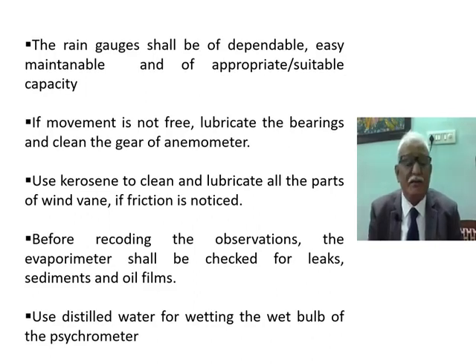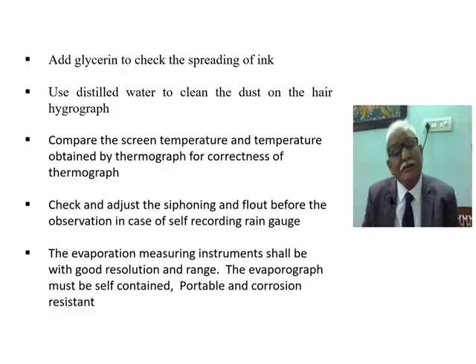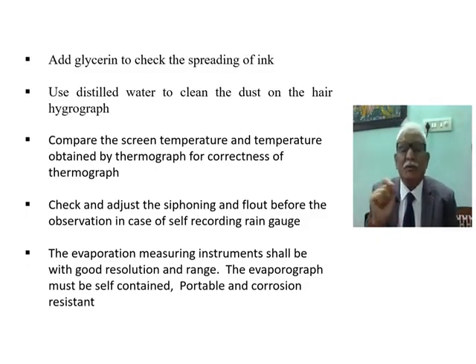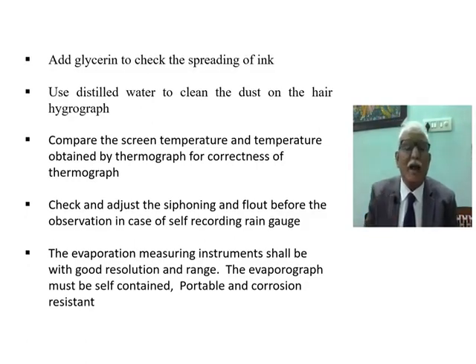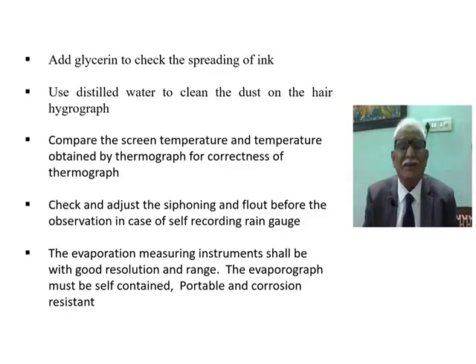Before recording, observations shall be checked for leaks, sediments, and oil films if any on the water surface. Use distilled water for wetting the wet bulb thermometer, which is very important. Also use water to clean the dust on the hair hygrograph, as the hair hygrograph gives continuous recording of humidity.